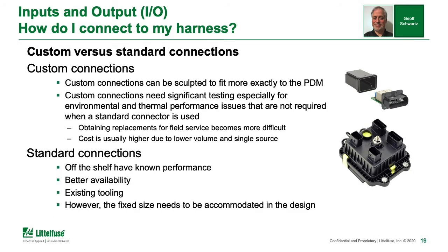So what type of connectors do I want to use? Custom connections are great because they can be sculpted to get the maximum I/O in the smallest amount of area on a PDM. The problem with custom connections is you've got to do a lot of environmental testing because there's no guarantee that that environmental testing will match with your custom PDM. And the other problem is field replacements. If you ever have to replace that connector, do you have access to the connectors? Can you find them? What's the cost of them also? Because they're obviously lower volume than standard connectors and therefore tend to cost more.